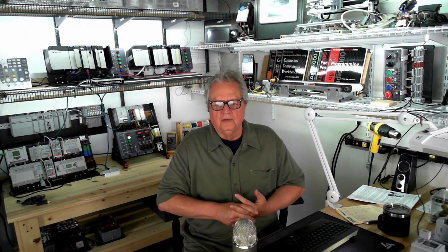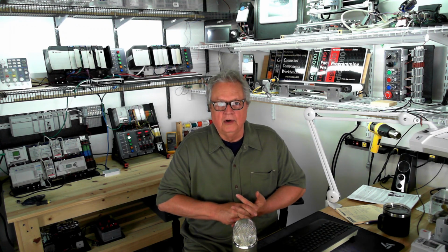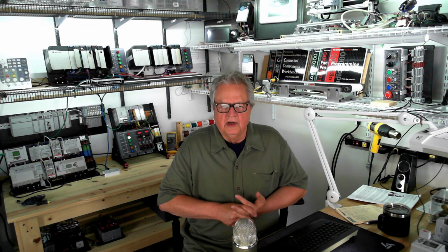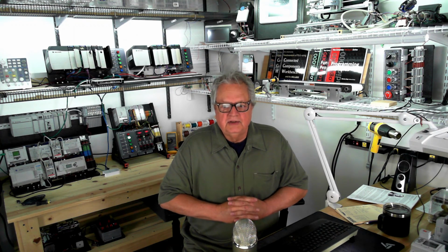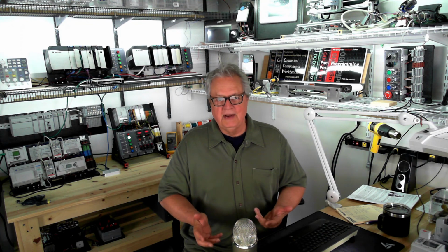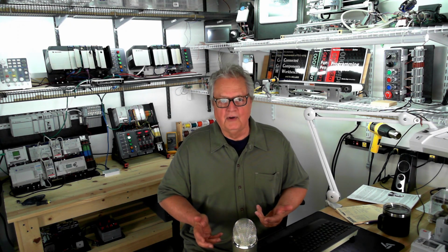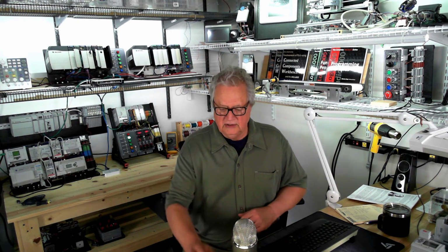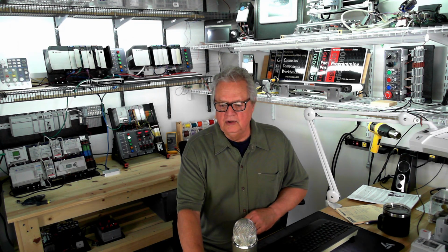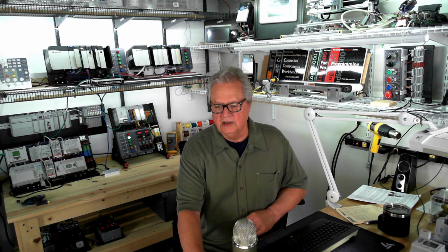And then your write instruction, direct coil or energize output. It's not really an output, but it looks like a relay coil. That's just simple. If the rung's true, then that instruction turns that bit on that it's addressing. If the rung's false, then it turns it off. So we just pretty much exhausted everything you could do with a single rung of logic, online, offline, etc.